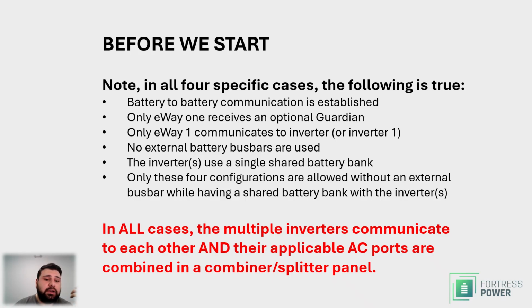This refers to all cases, not only these 4, but all cases in general. So in all cases, the multiple inverters communicate with each other, and their applicable AC ports are combined in a combiner/splitter panel. So what this says really is that the inverter to inverter communication is mandatory. You must have it. When inverters communicate with each other, they must support the same load panel or the same group of load panels. That is also a requirement. And that's why we see combiner panel here.